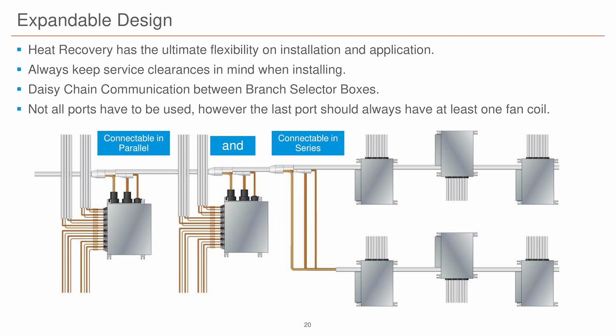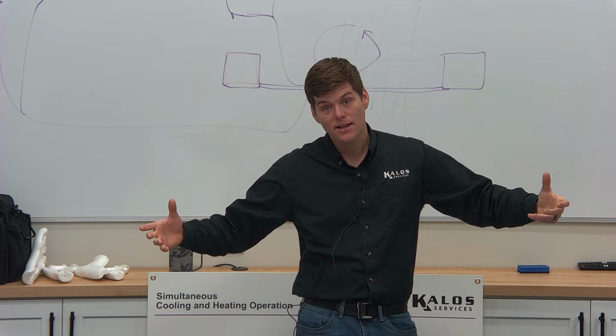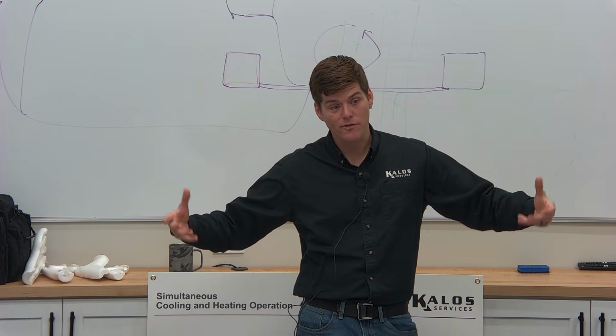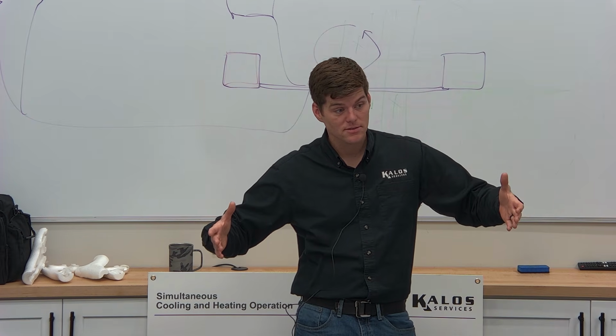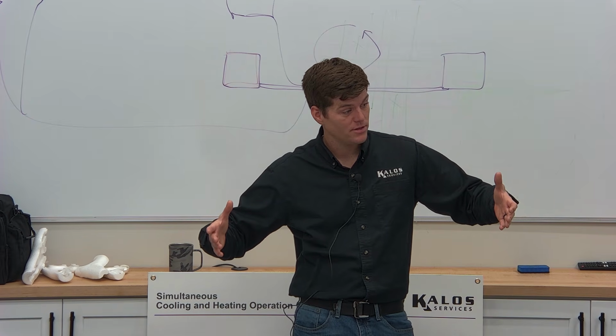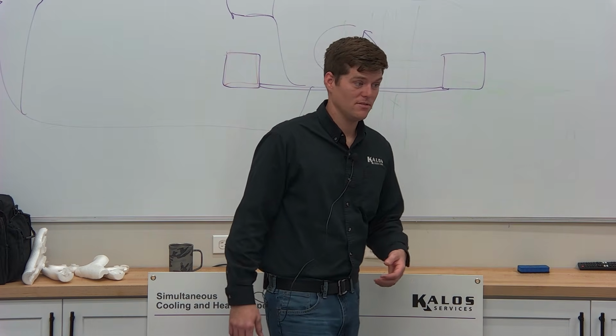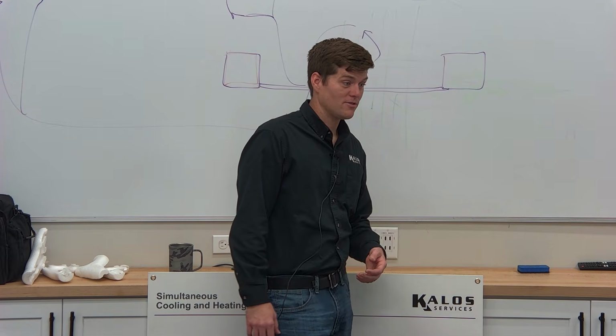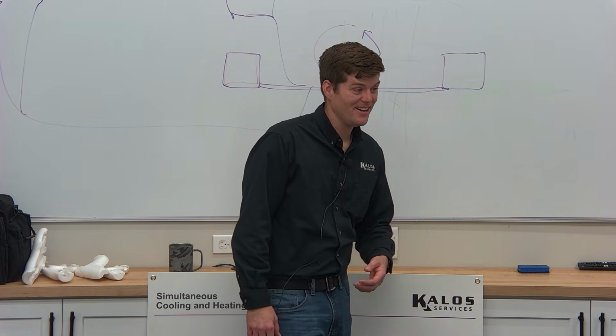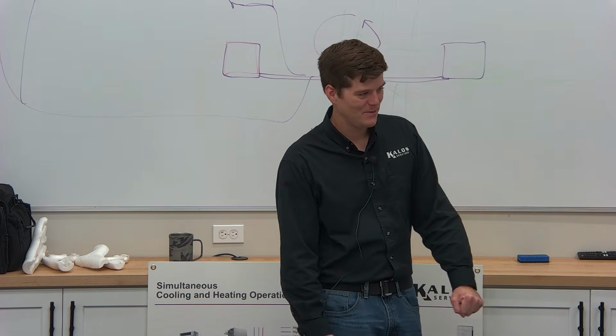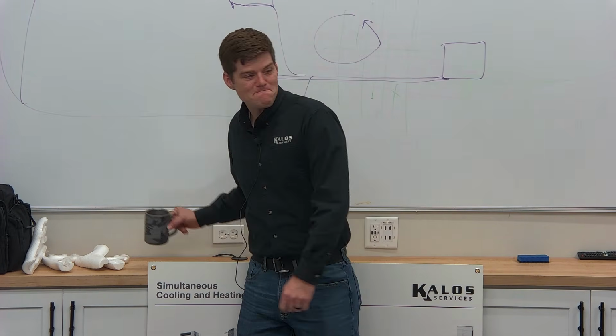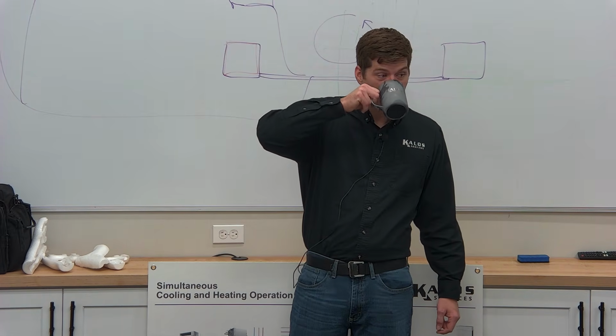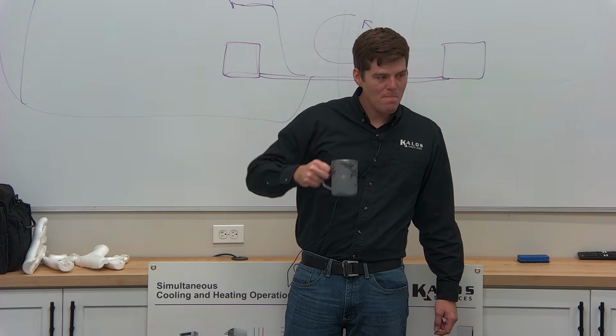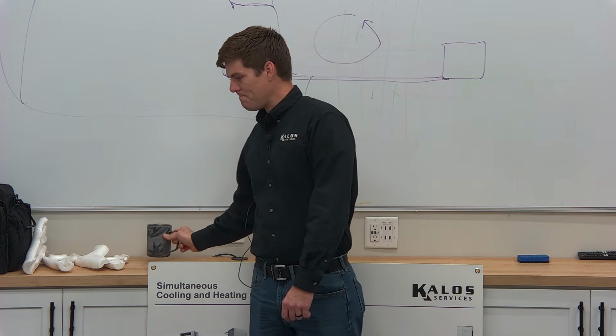So this is your typical VRF system, whether it's multifamily or whatever have you. They have boxes that will actually support up to 12 indoor units on one box, for one specific zone. Some manufacturers have 18. Imagine cross-wiring and piping on that. It's a lot of fun. Those boxes, all 18 units on one box, can either run heat or cool at the same time, any given time.